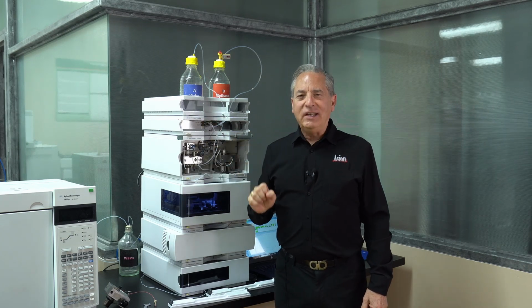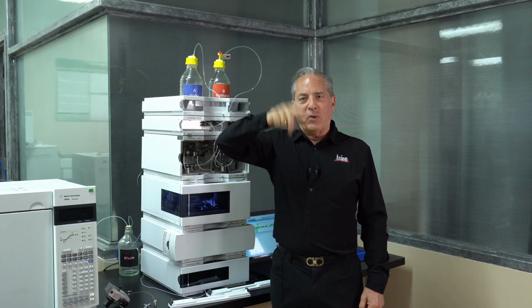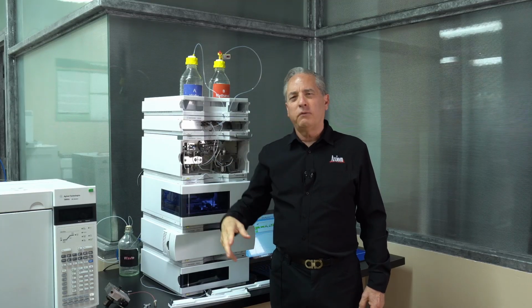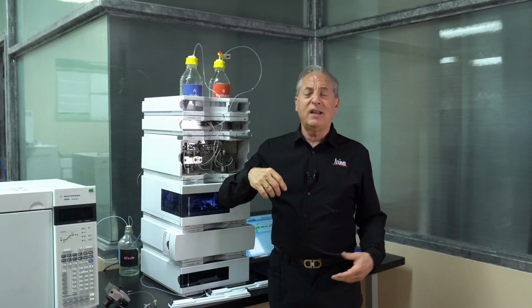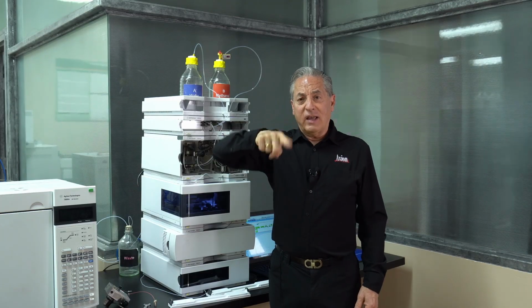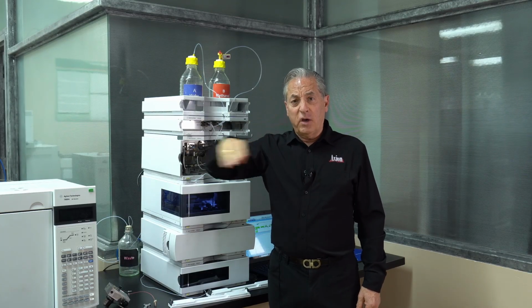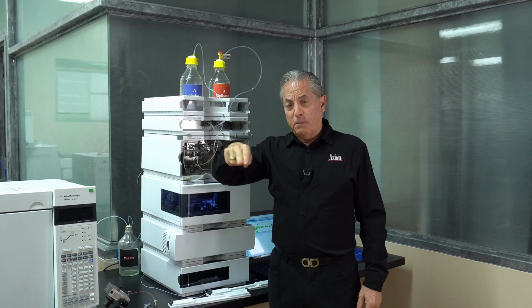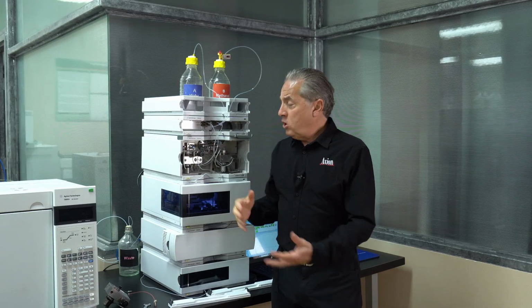As opposed to detector noise. Detector noise is just random. Whether you've got a broken flow cell, drips on it, condensation on it, or a light bulb going bad, you're going to get random noise. So this is detector noise, and this is pump noise. When we see pump noise, we know we have an issue.